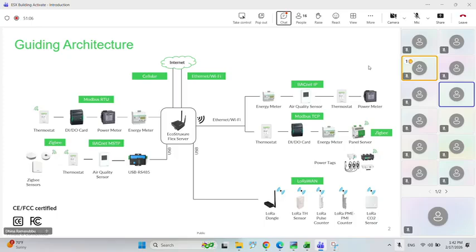Yeah, you can. If we have a device connected to the RPC, how is this counted? Do we count only the RPC as one device, or the devices connected? No, RPC is not considered as one device. Inside the RPC, we create registers as BACnet registers. Consider we are controlling one air condition. The points we have are on and off control, a temperature sensor, and a status for monitoring the other points of the same air condition. Whichever points we mapped for that air condition using the IO points will be created as one device.